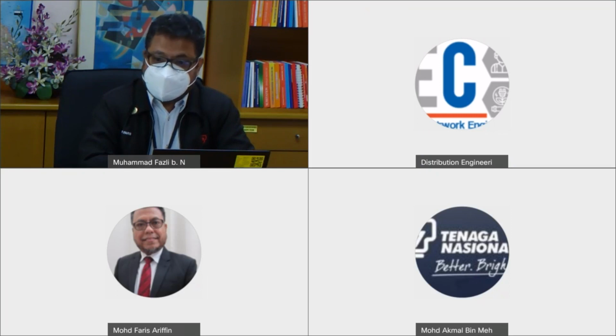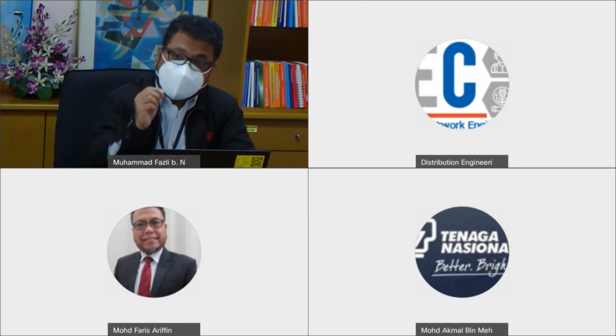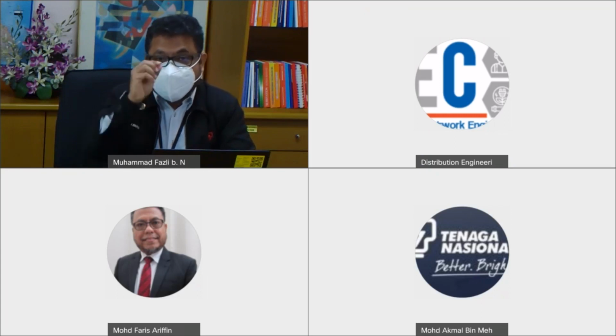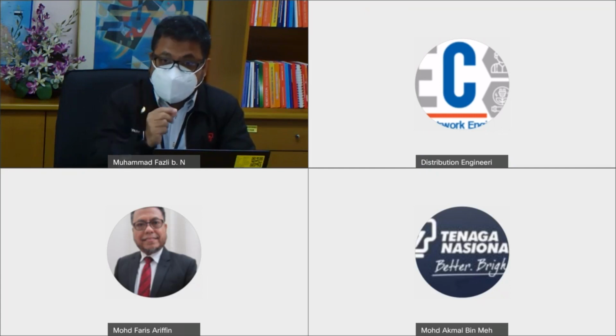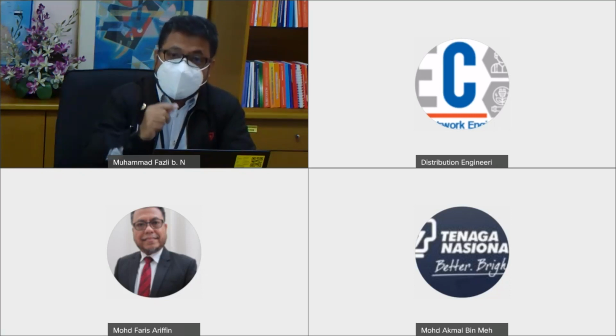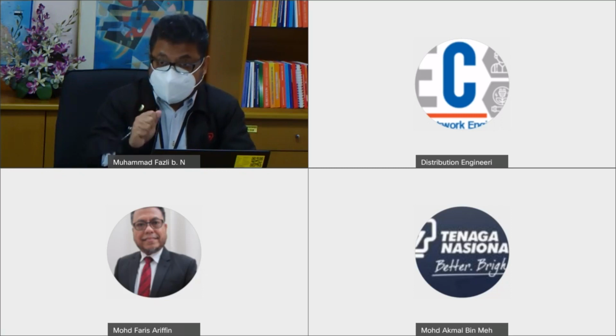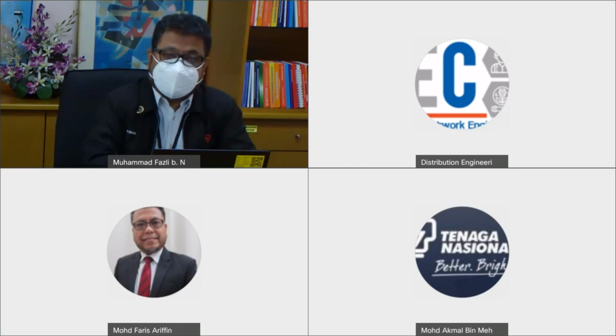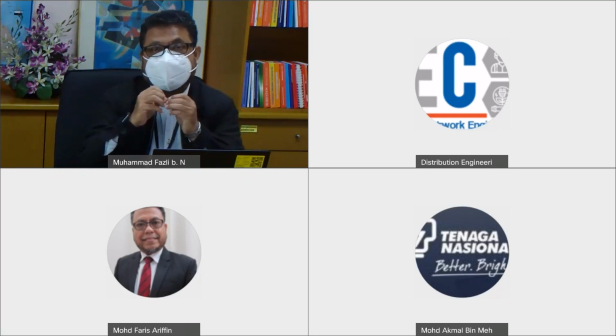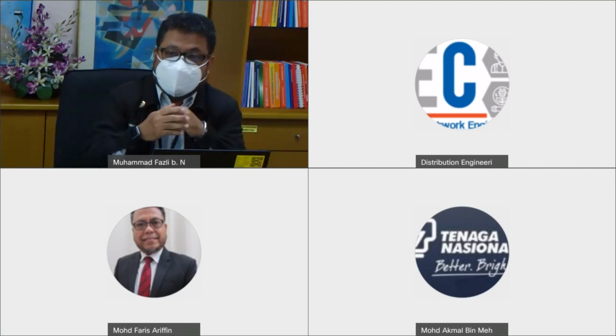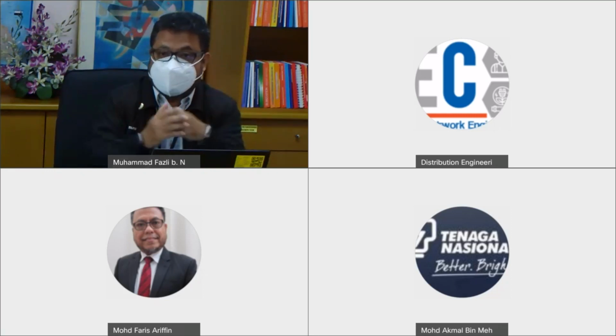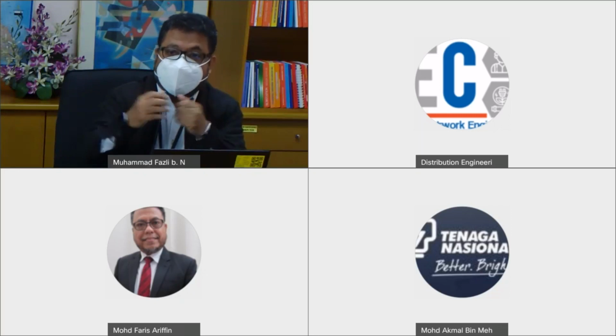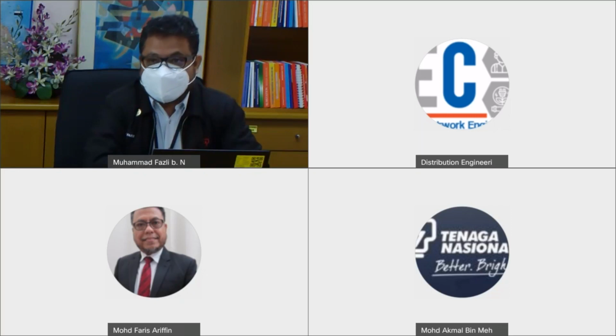And then, for example, when it is in wet condition, the water will seep into the micro cracks, causing a direct path from the live conductor to the earth. It develops into leakage current, and as the leakage current develops, it will become a fault. So that will cause the transient tripping. But when the transient tripping occurs at very high current or high voltage level, the water will dry. So that's why the tripping will be clear, because the water inside the porcelain will be dry. So that is the nuisance that I can think of, why we migrated from using porcelain to glass later. I hope that answers your question.